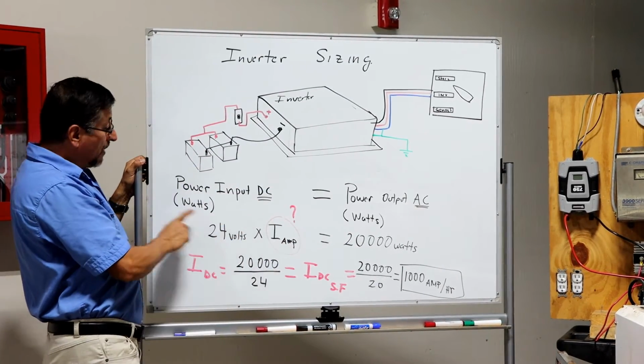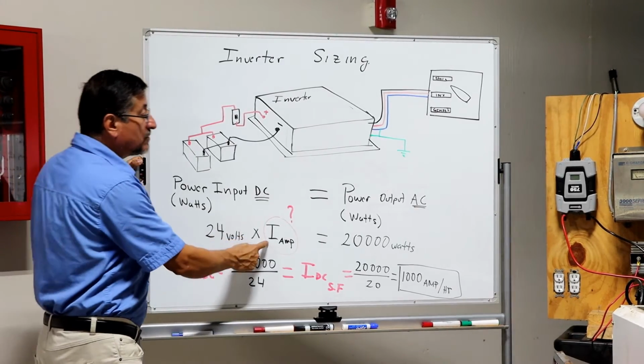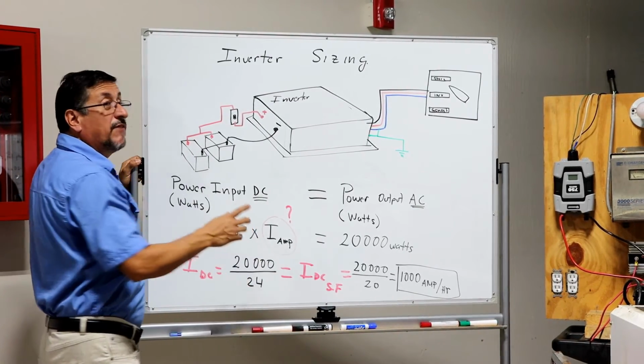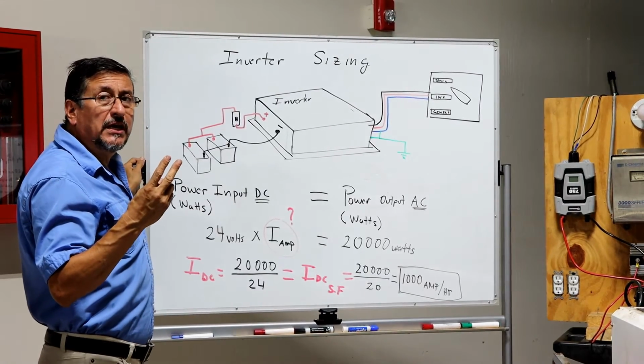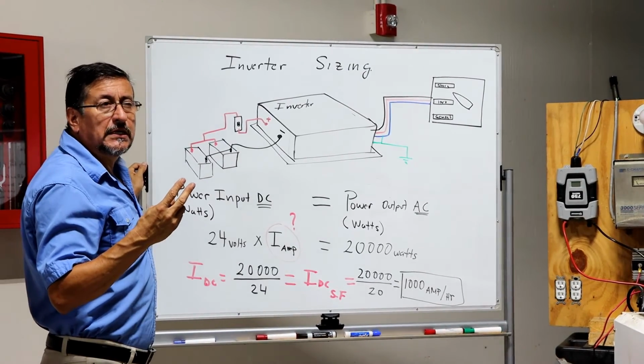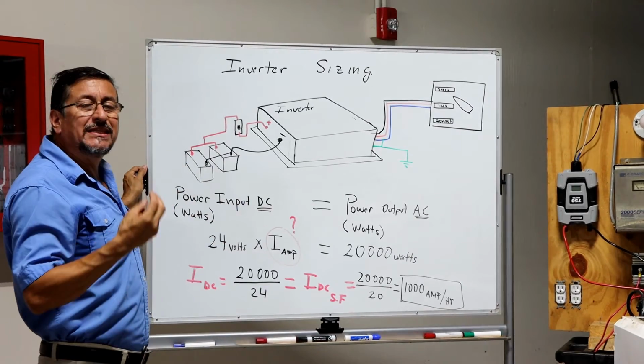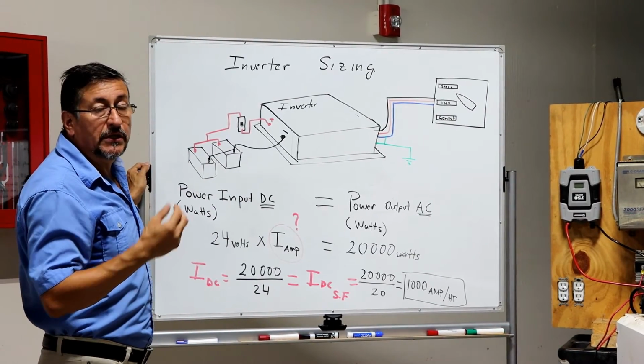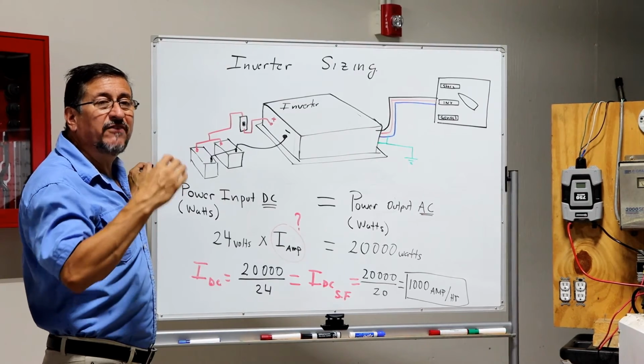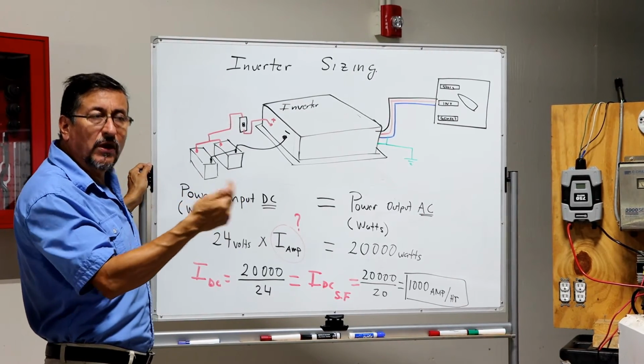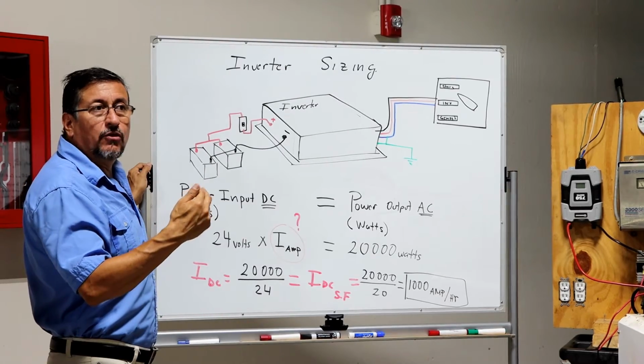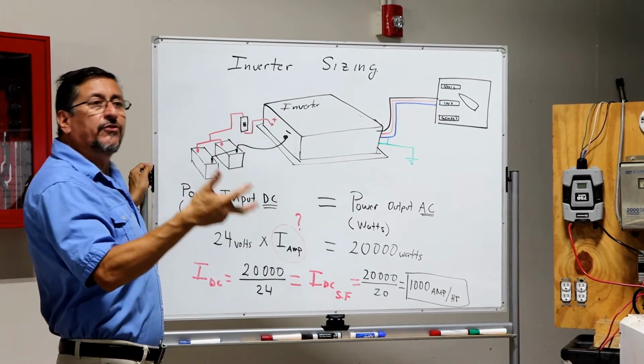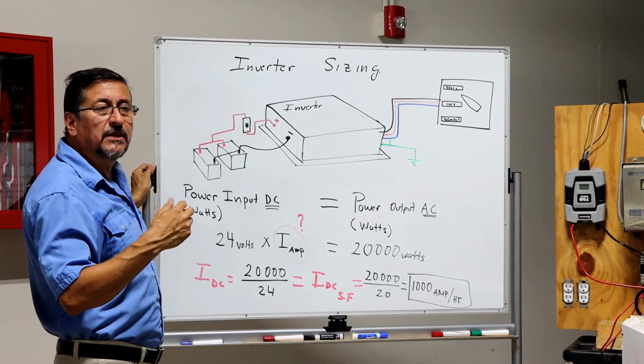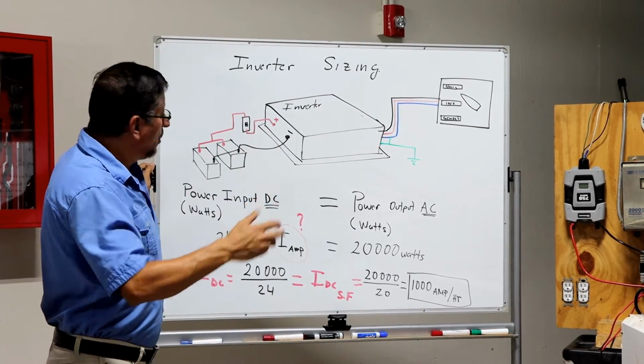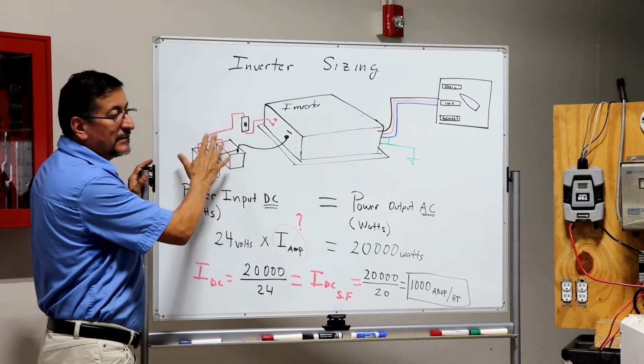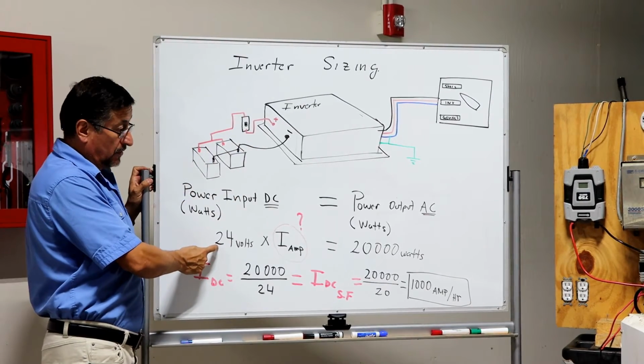What is the formula for power? The formula for power is voltage times intensity. Remember, if I need 2 phases in the output, 240 volts, normally the configuration in the input DC should be 24 volts. Because remember, in the previous episode, we have a step-up transformer. If I have 12 volts in the batteries, I am going to produce 120 volts. If I have 24 in the configuration on the batteries, I am going to produce 240 volts. I am going to connect those batteries in series in order to produce 24 volts.